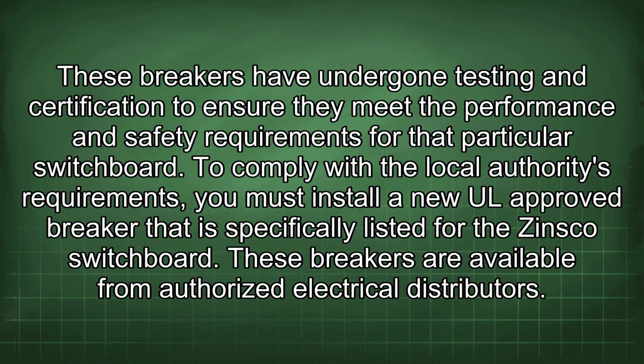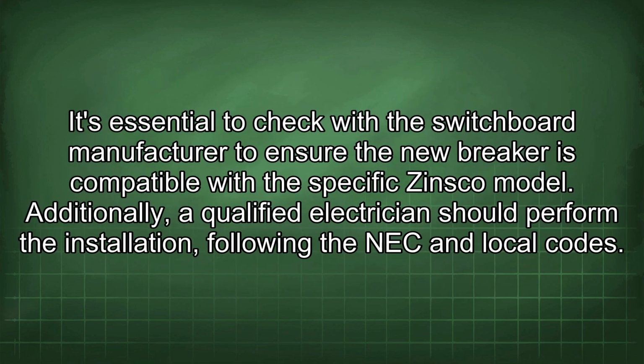These breakers have undergone testing and certification to ensure they meet the performance and safety requirements for that particular switchboard. To comply with the local authority's requirements, you must install a new UL-approved breaker that is specifically listed for the Zinsco switchboard. These breakers are available from authorized electrical distributors. It's essential to check with the switchboard manufacturer to ensure the new breaker is compatible with the specific Zinsco model. Additionally, a qualified electrician should perform the installation following the NEC and local codes.